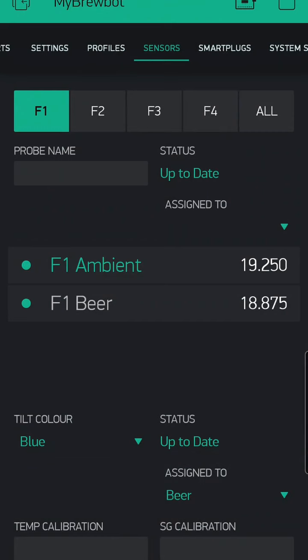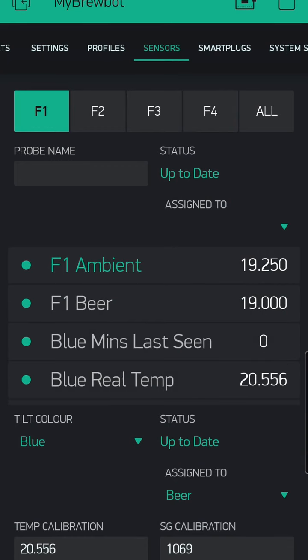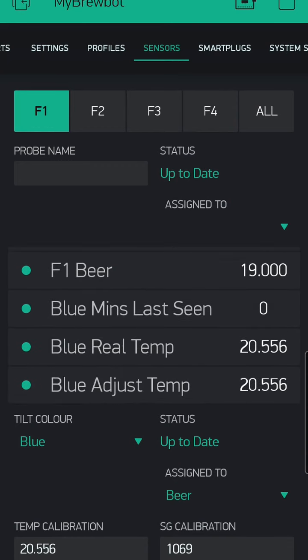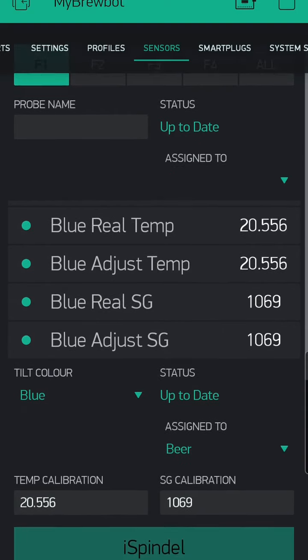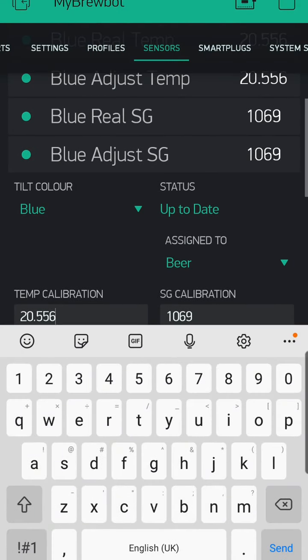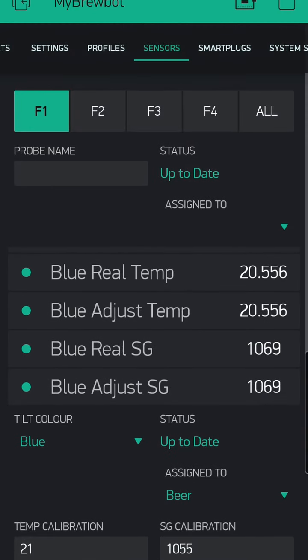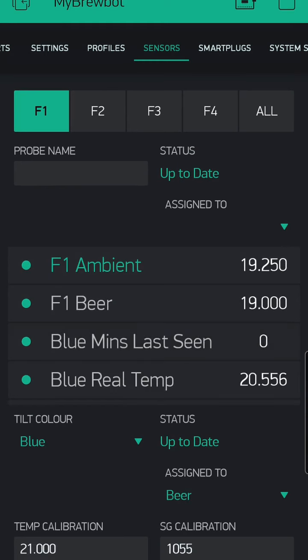To calibrate your tilt, enter the calibration values into the temperature and specific gravity fields. The controller will do the math. You just need to enter the measured values. The controller will work out the variances. Remember, specific gravity is input as a whole number. For example, a specific gravity of 1.055 needs to be input as 1055.